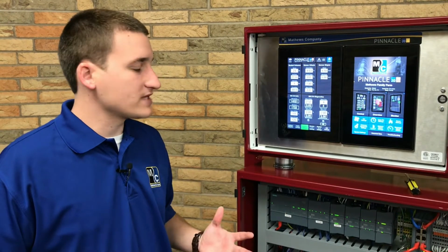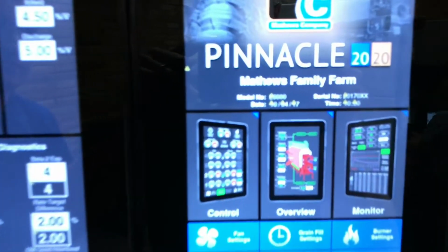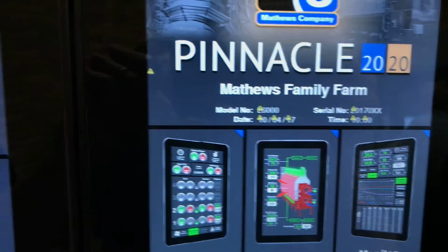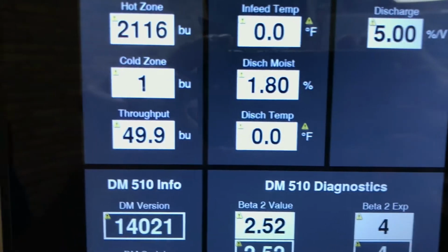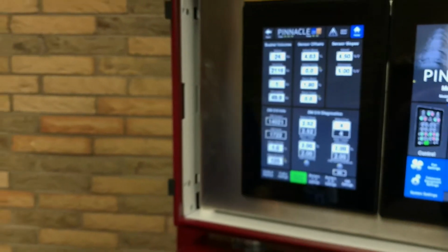So, one of the most common issues that we may see is yellow triangles on the HMI screen. These triangles look like the ones you see here. We can see on the home screen, by any PLC inputs, as well as on any other screen where you have PLC values or tags. Those yellow triangles tell us that the HMI and the PLC are not talking to one another.